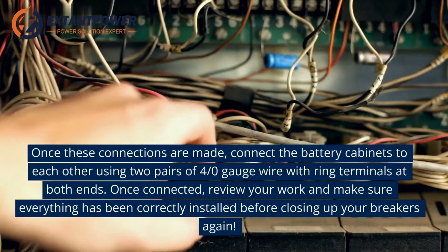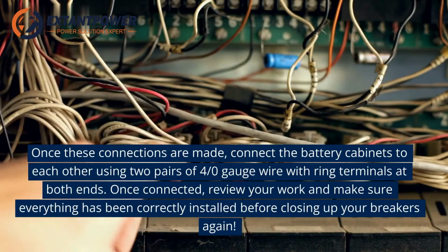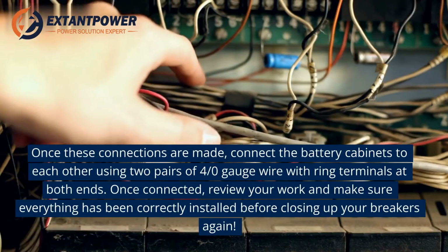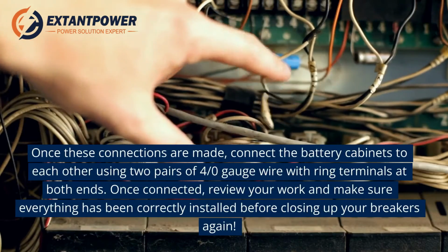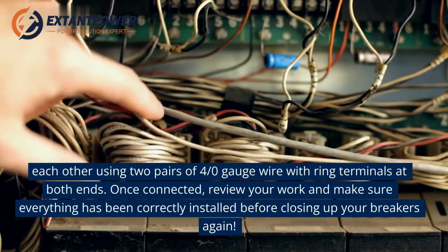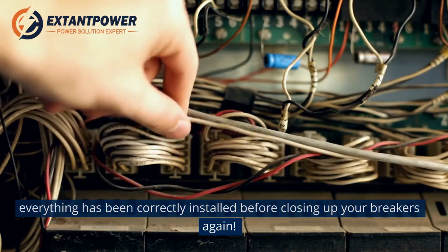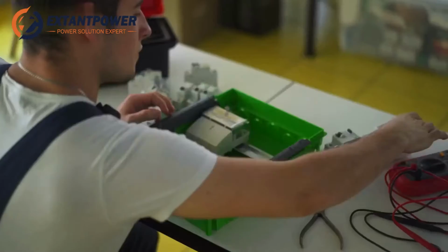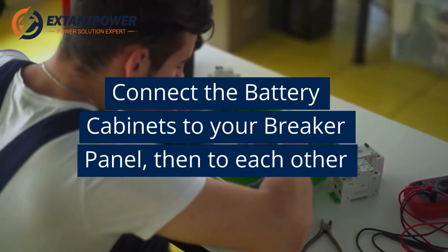Once these connections are made, connect the battery cabinets to each other using 2 pairs of 4/0 gauge wire with ring terminals at both ends. Once connected, review your work and make sure everything has been correctly installed before closing up your breakers again. Connect the battery cabinets to your breaker panel, then to each other.